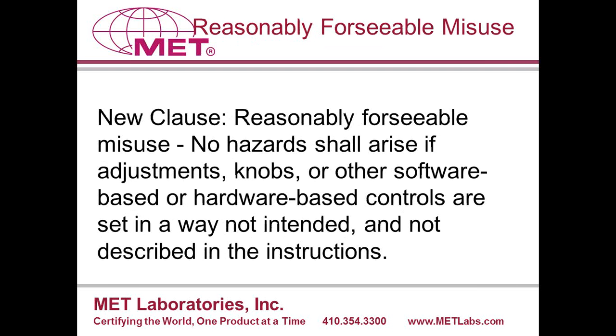Another new term is reasonably foreseeable misuse. In the previous edition, it was sufficient to have a clause in your manual stating that if a product was used outside of its normal operation, then the protection provided by the equipment may be impaired. With the third edition standard, the manufacturer must consider the possibility that a product will be misused and design safety features to address this possibility.